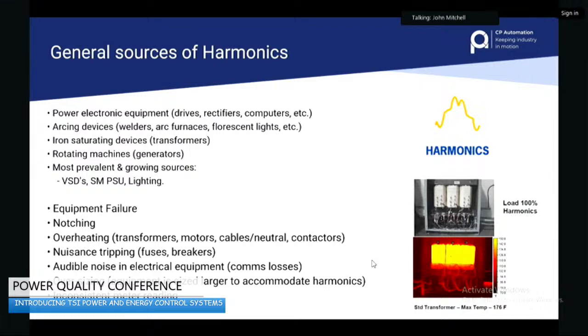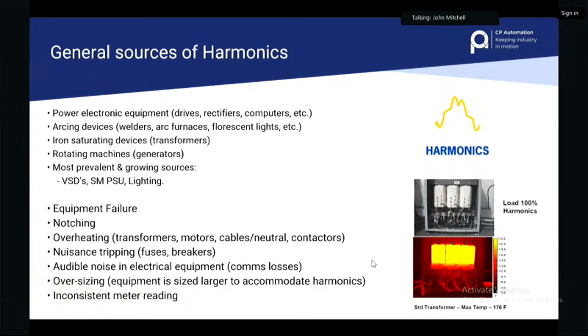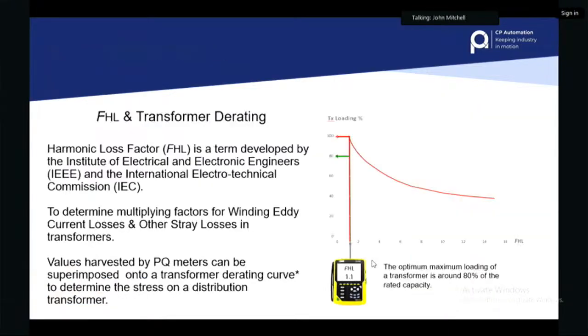What can happen is if you get too many harmonics caused by all the different loads, they summate at the transformer and cause it to overheat, as you can see in this picture here on the bottom right. There is something else I'll get into in a second, which is causing transformers to derate, called FHL, similar to K factor. It's called harmonic loss factor, FHL, and we'll come to that in a second. But yeah, there are a lot of problems that can occur when your transformer's not happy, so let's keep it happy. So this is FHL, and what FHL basically means is that it's a way of working out: is your transformer happy? Are the loads that are being drawn affecting the transformer's capability to keep a stable voltage, a healthy voltage, without distortion?